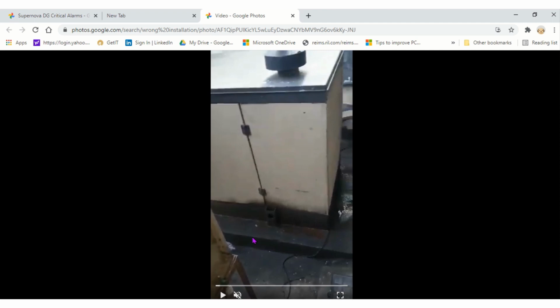So this is what I want to show here. At least with that, we can have proper due diligence when we acquire the space and see the clearance. We have to have enough clearance for the maintenance people to carry out preventive maintenance effectively. If there is no proper clearance, and there is a lot of hindrance, then definitely a person cannot do qualitative preventive maintenance, which leads to premature failure and higher operational cost of the DG set.